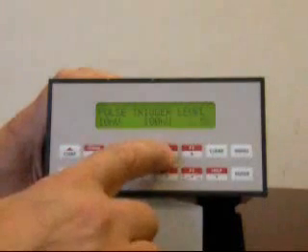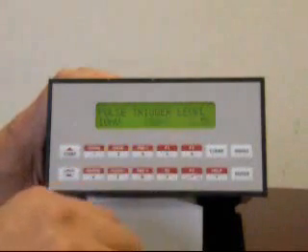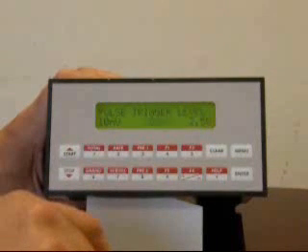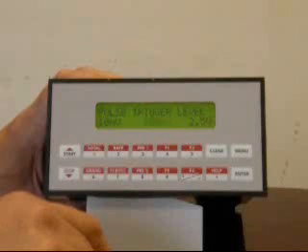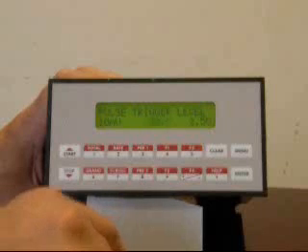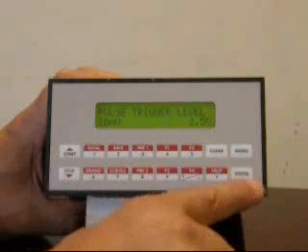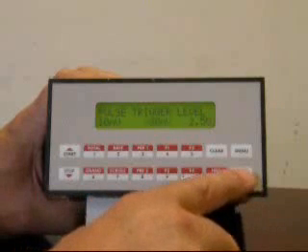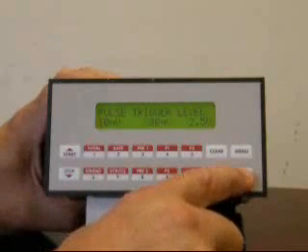Next, there's a selection for the pulse trigger level to use. On our example of a 2 inch turbine flow meter, a selection of 100 millivolts or 10 millivolts would be considered suitable selections. The 10 millivolts selection would be used to obtain the maximum range from the flow meter. The 100 millivolts would be selected for noisier applications where the signal from noise pickup may be greater than 10 millivolts during periods of no flow. I'm going to choose the 100 millivolts selection here.